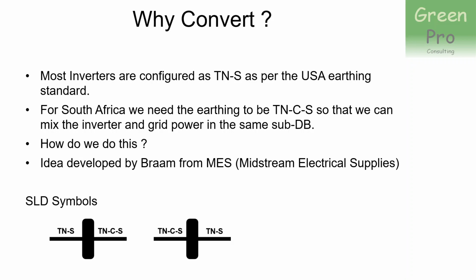Most inverters are configured for the USA, because that's probably where everybody aims at in terms of the inverters. They are configured as a TNS system because that is what they use in the US. In South Africa, we use a TNCS earthing system. And if we want to feed inverter power as well as grid power to the same DB or the same sub DB, or anywhere in, call it your house, then we have to have one consistent earthing system.